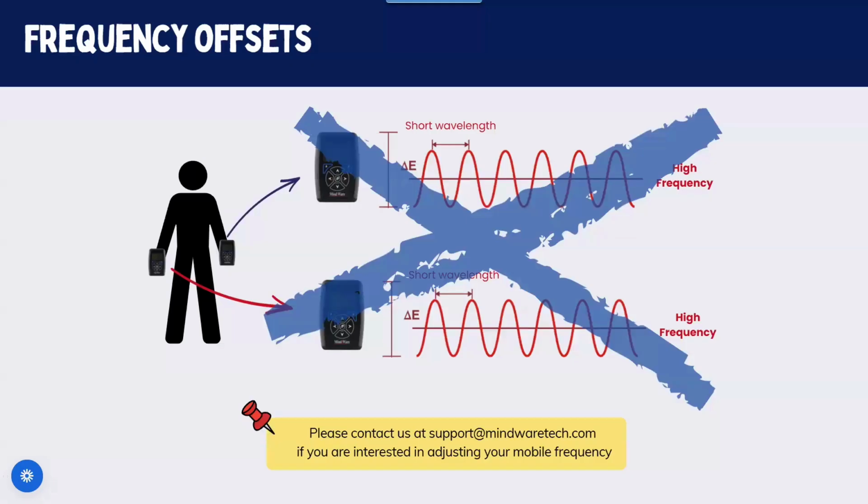So that being said, if you are concerned or you want to test this to see if we do have frequency offsets, what I would recommend is following the steps of today and going through and essentially putting the mobile on the chest, putting the mobile on the calf, and then seeing in BioLab in your preview screen if we have clear Z0 and DZDT data. This interference will be very obvious to you. Very, very, very obvious. It's thick, it's big, you can't see really anything underneath the waveform. So I would recommend doing a little test run on yourself to see if there's no interference observed.